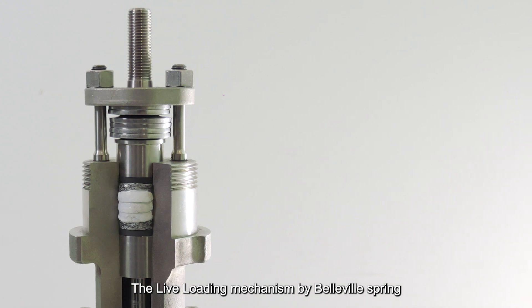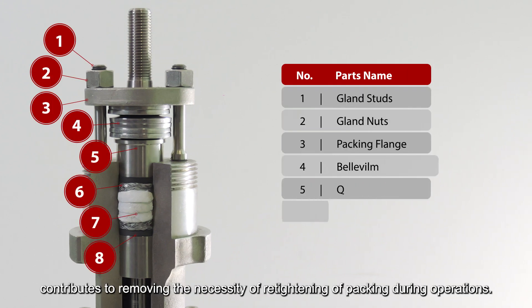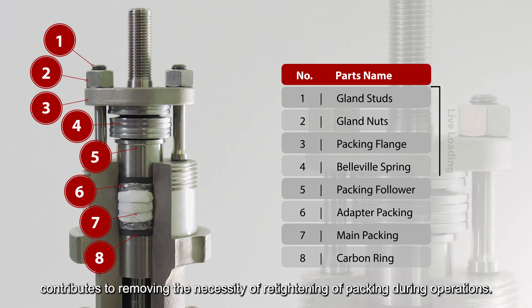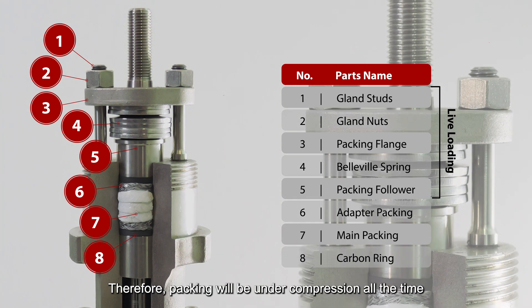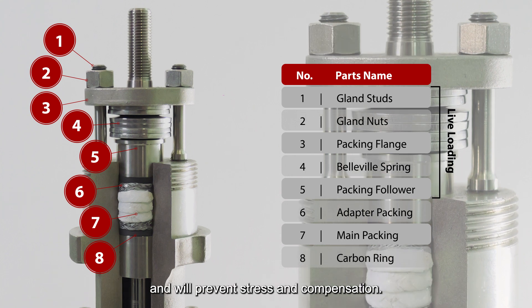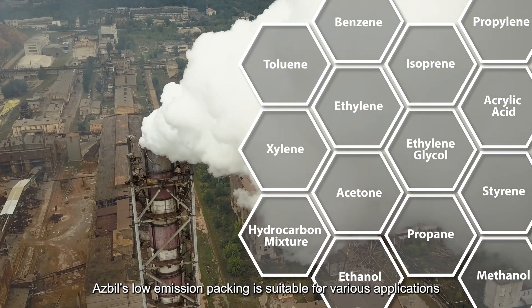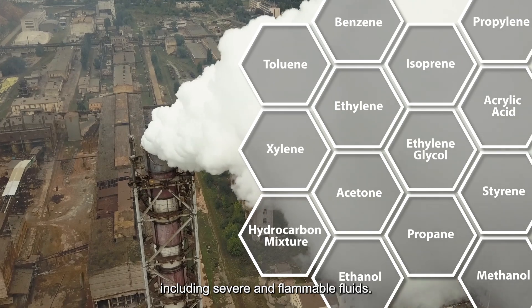The live loading mechanism by Belleville Spring contributes to removing the necessity of re-tightening of packing during operations. Therefore, packing will be under compression all the time and will prevent stress relaxation. Azbil's low emission packing is suitable for various applications including severe and flammable fluids.